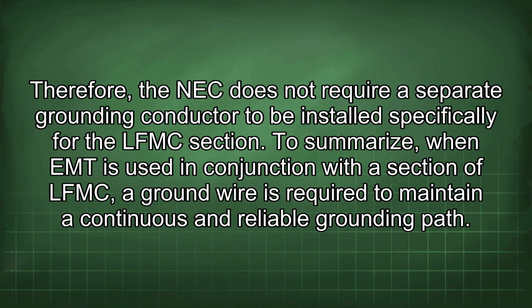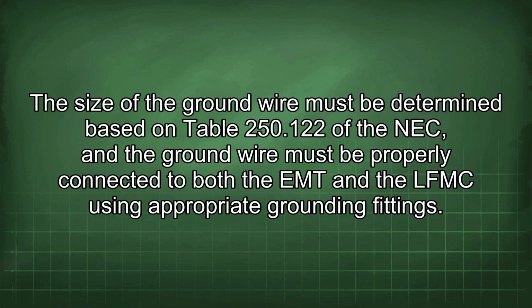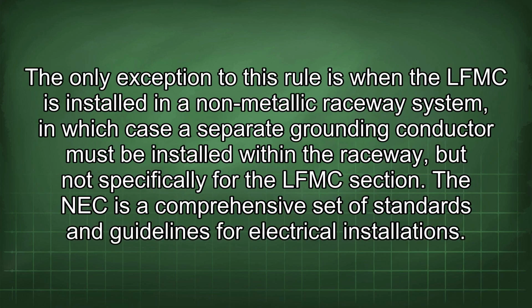To summarize, when EMT is used in conjunction with a section of LFMC, a ground wire is required to maintain a continuous and reliable grounding path. The size of the ground wire must be determined based on Table 250.122 of the NEC, and the ground wire must be properly connected to both the EMT and the LFMC using appropriate grounding fittings. The only exception to this rule is when the LFMC is installed in a non-metallic raceway system, in which case a separate grounding conductor must be installed within the raceway, but not specifically for the LFMC section.